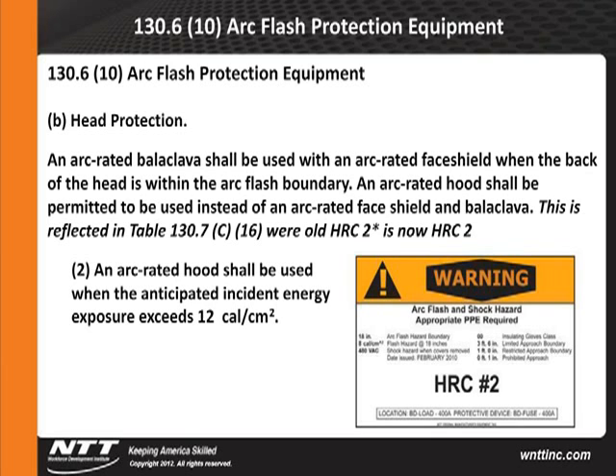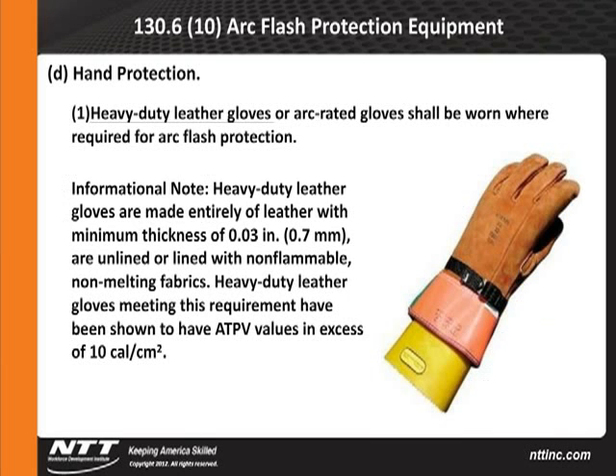So it goes on to say this is reflected in Table 16, where the old 2 is now HRC 2. An arc-rated hood shall be used when the anticipated incident energy exposure exceeds 12 cal per centimeter squared, the full hood. What about hand protection? Heavy-duty leather gloves or arc-rated gloves should be worn and are required for arc flash protection. Now, if you're wearing voltage-rated gloves and the leather that comes with them, that will meet the standard, but I can't simply go out there and get a real lightweight pair of leather for my other type of work.